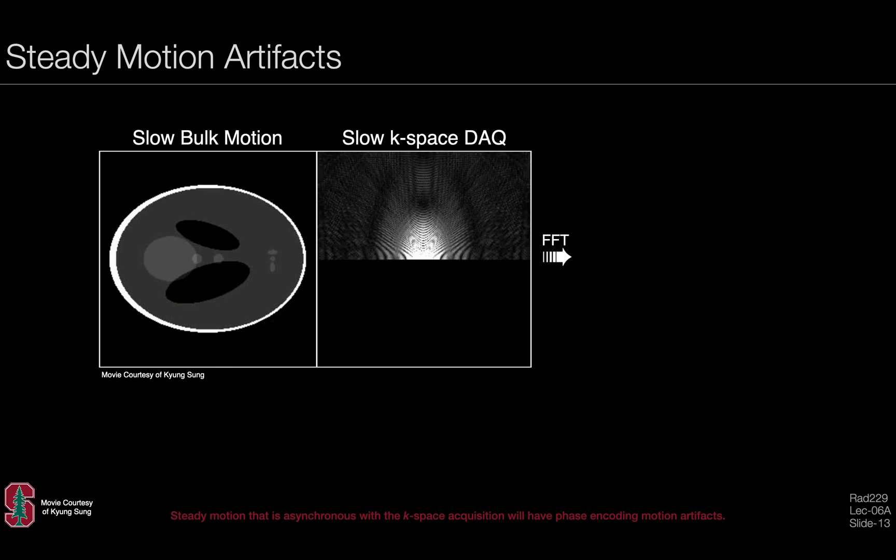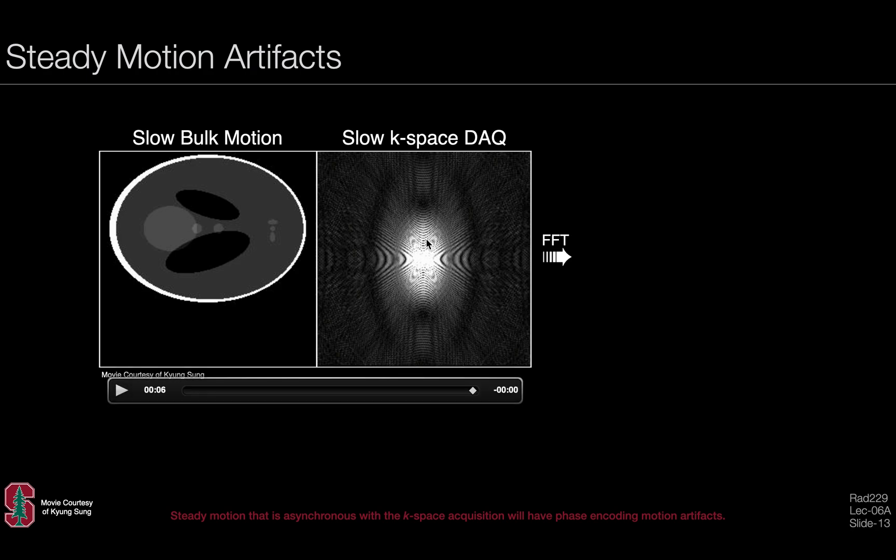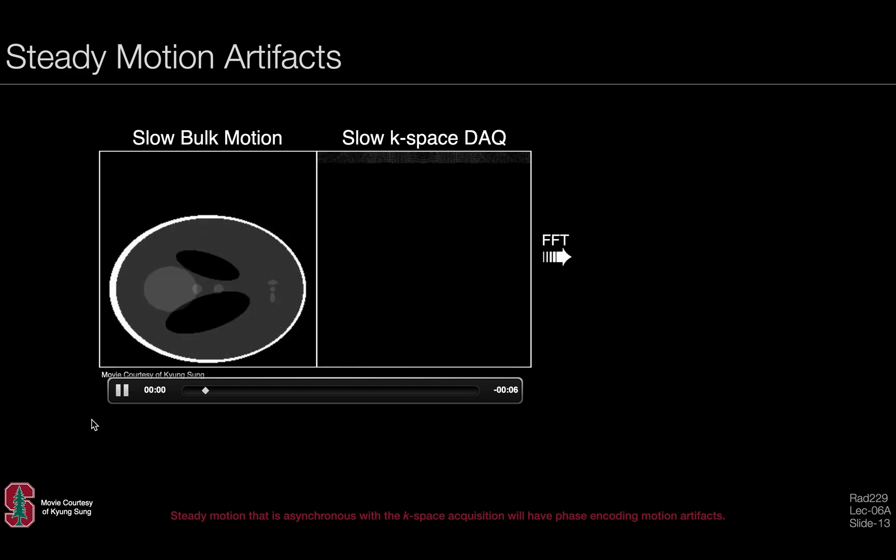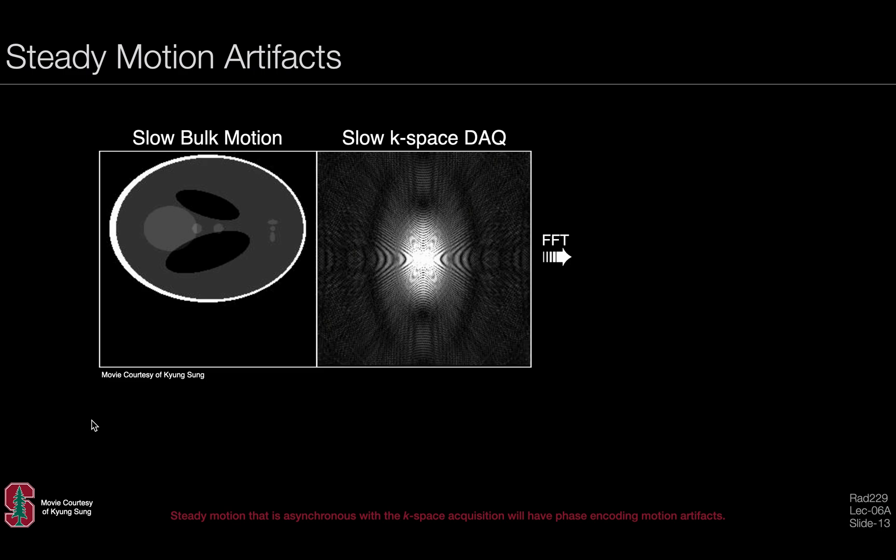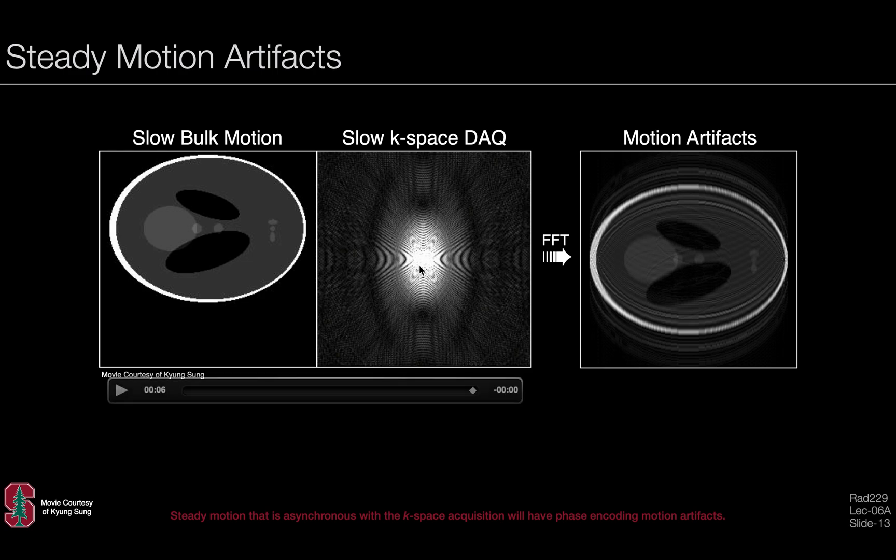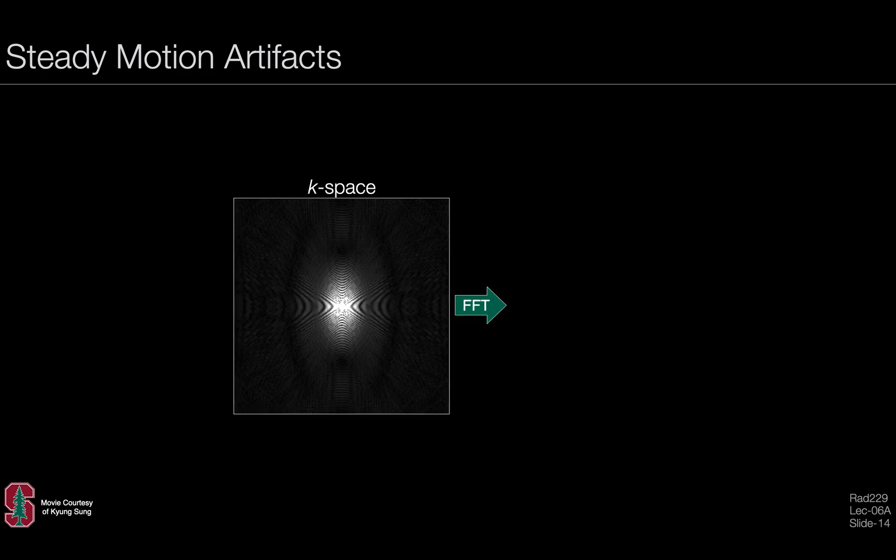Why does this happen? Here's a nice example. This movie was lent to me by Kyung Sung at UCLA. On the left-hand side, we have an object that's undergoing slow bulk motion. On the right-hand side, we have a k-space trajectory. Imagine that this object is moving while the data is being acquired, and the k-space trajectory is such that we're filling from the top of k-space to the bottom of k-space. Watch again as the object moves up and the k-space acquisition moves from top to bottom, so they're in opposition to one another. If we take the Fourier transform of the acquired k-space data during object motion, we get an image with clear and distinct motion artifacts that obscure information or your ability to see features in the underlying object.